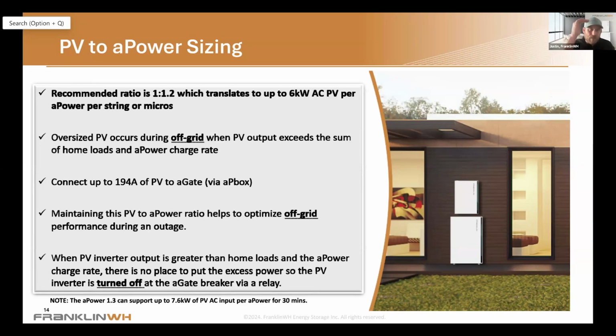In terms of max ratio—for the technically minded, I know you've been wondering why we didn't talk about this sooner—we do have ratio sizing. Think of it this way: if I'm doing a single battery system and want the solar to work when the grid goes down, it needs to be 6 kilowatt or lower on a micro, 7.6 or lower on a string. Or we can use the AP box, which lets you combine larger systems—using part of it in the morning when a 10 kilowatt system is running at 5, then shedding down to 5 kilowatt at 2pm when the system would otherwise be running at max.